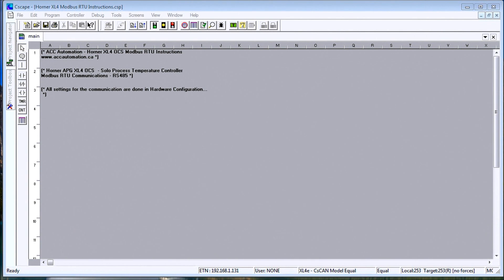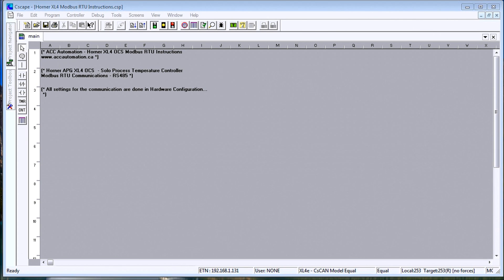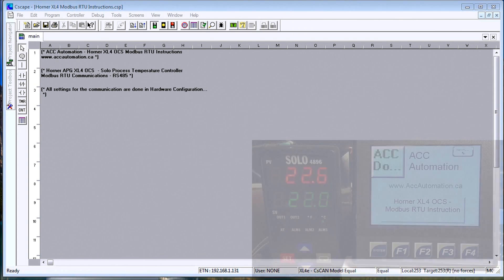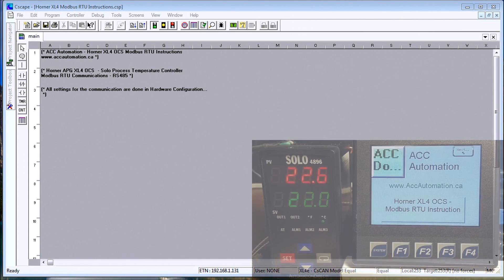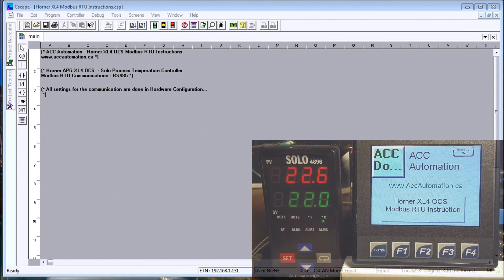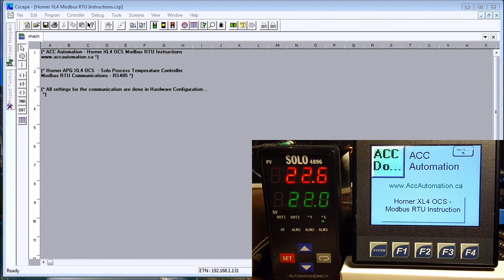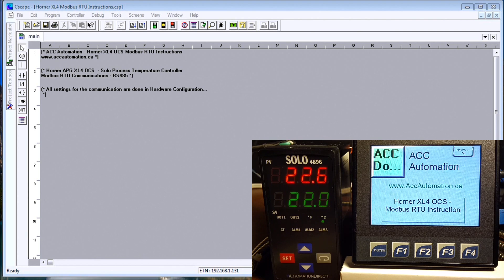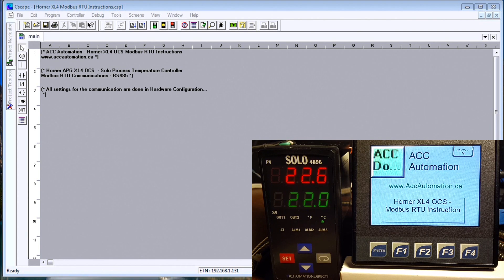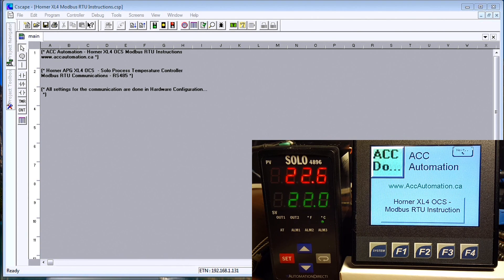Hi everyone, today we're going to be looking at communicating from the Horner XL4 all-in-one controller to the SOLO process temperature controller. We're going to be using Modbus RTU as the protocol to communicate serially on RS-485. There are three steps involved, and the first step is to do our wiring of our system.